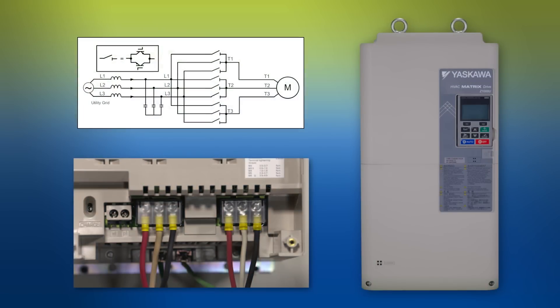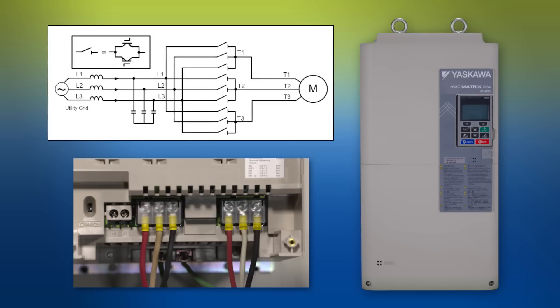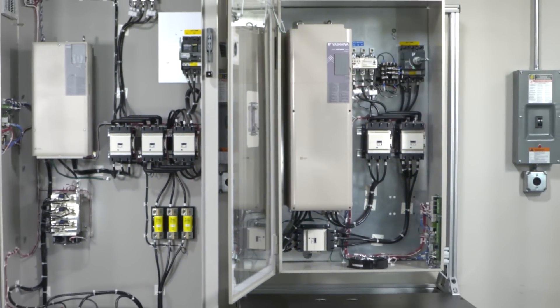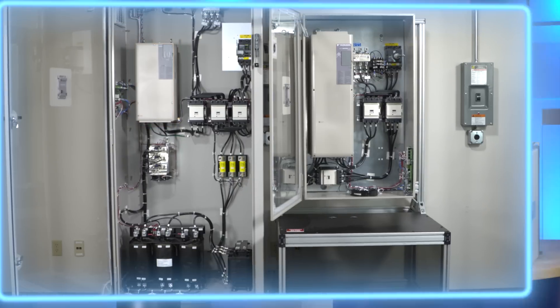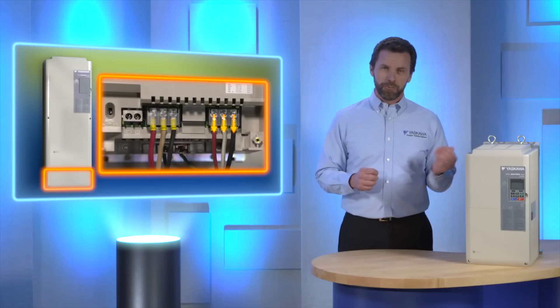The matrix drive directly converts the three-phase AC input to the variable AC output required for precise control of voltage and frequency to the motor. The matrix drive is different from general purpose inverters because U1000s do not need additional external hardware, including filtering and multi-pulse configurations used to prevent harmonics. There is no DC link circuit with diodes and electrolytic capacitors. This results in a greatly simplified design — three wires in and three wires out.